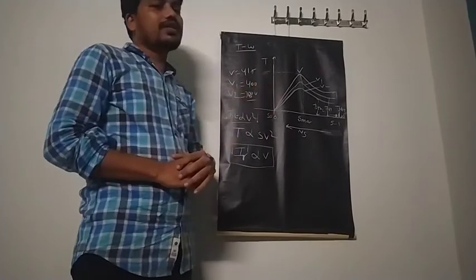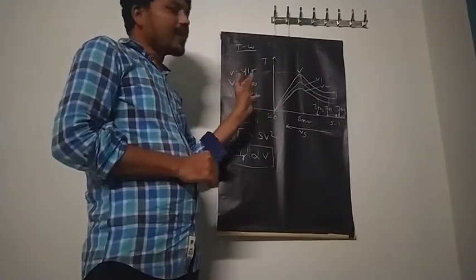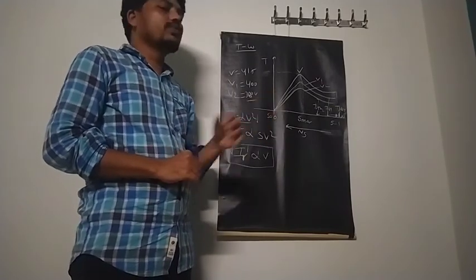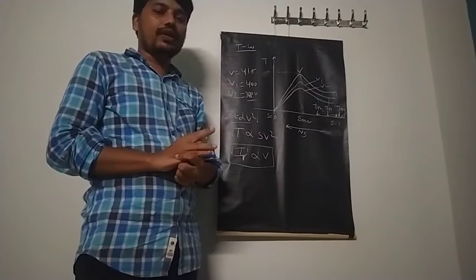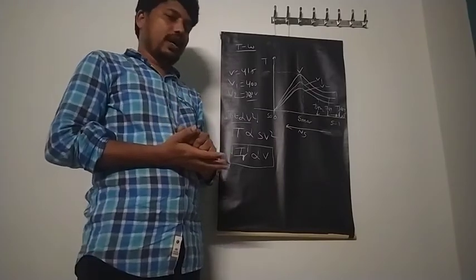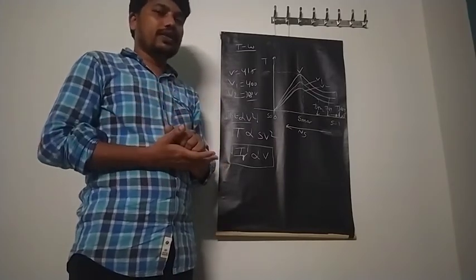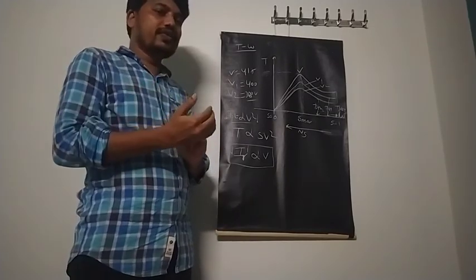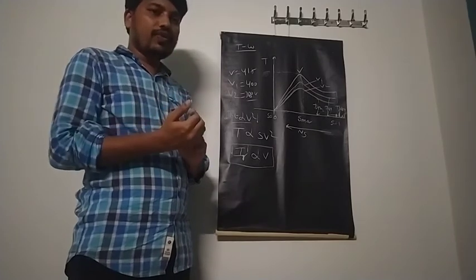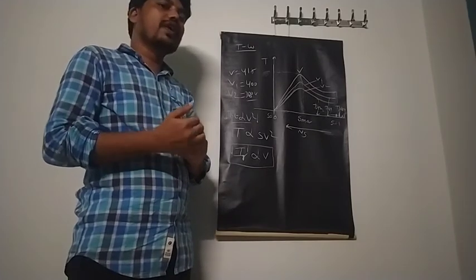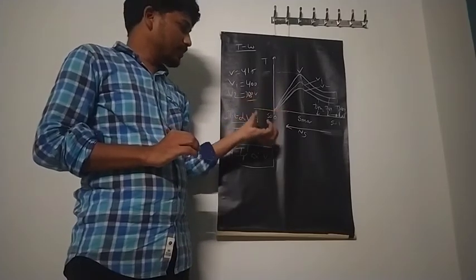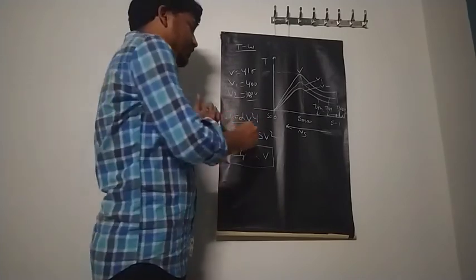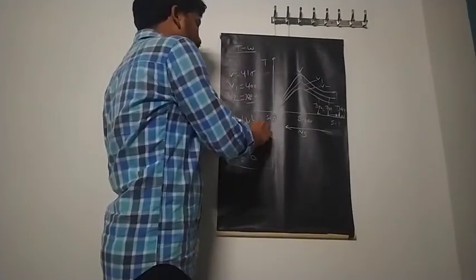From these characteristics we can conclude that the stator voltage control method using the AC voltage regulator is best suitable for pump or fan type drives, where the torque reduces and the speed reduces. Whenever we decrease the voltage, torque reduces, then speed also reduces, because to maintain a constant torque, the slip value should increase.